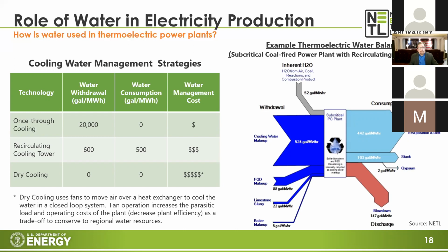Recirculating cooling towers, on the other hand, require mechanical draft towers to be built, managed and operated, but their water withdrawal is much smaller, around 600 gallons per megawatt hour, while water consumption is about 500 gallons per megawatt hour—significantly different than once-through cooling systems.